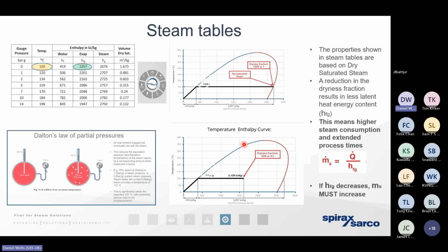If the steam was 50% dry, 50% wet, there'd only be 50% of the useful heat energy present within the steam. That could mean two things. It could mean that we got very, very wet steam, perhaps as a result of poor boiler control or poor condensate removal from the infrastructure. But because the steam was significantly wetter with less energy contained within it, it would mean that either the heat exchanger was undersized and we couldn't get the amount of heat required by the process across that thermal barrier at the appropriate rate. Or it could mean that the boiler has to work significantly harder to produce twice the mass of steam that was expected because there's half as much energy contained within it.